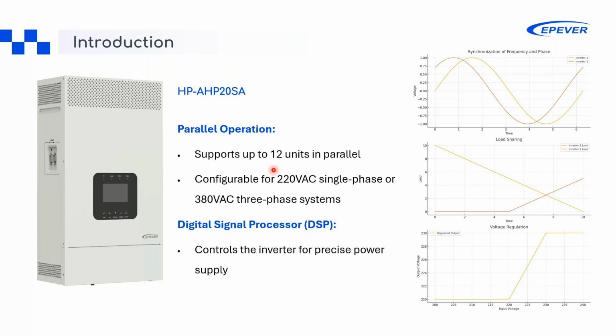There are some challenges related to parallel communications in the inverter world. In the top graph, we have two sine waves representing the output voltages of two inverters. For successful parallel operation, these waves must be synchronized in both frequency and phase; any discrepancy can lead to circulating currents, causing inefficiencies and potential damage. This requires accurate, fast digital signal processing to keep the waves synchronized so the power output is smooth and effective without losses.